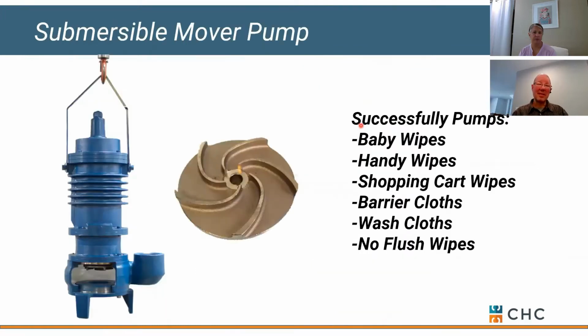The last one that's a little unique is what we might call a mover or a vortex pump. This simply uses a skinny impeller that's tucked up into the housing and works more on a vortex setup. So we still move the water, but any rags or wipes that might get wrapped around that impeller don't have a very good chance to do that because the impeller is so skinny. So this works really well for people who are having problems with people flushing baby wipes or hand wipes, any sanitary rags. Obviously, we're seeing that in a COVID situation, a lot of disinfection going on.